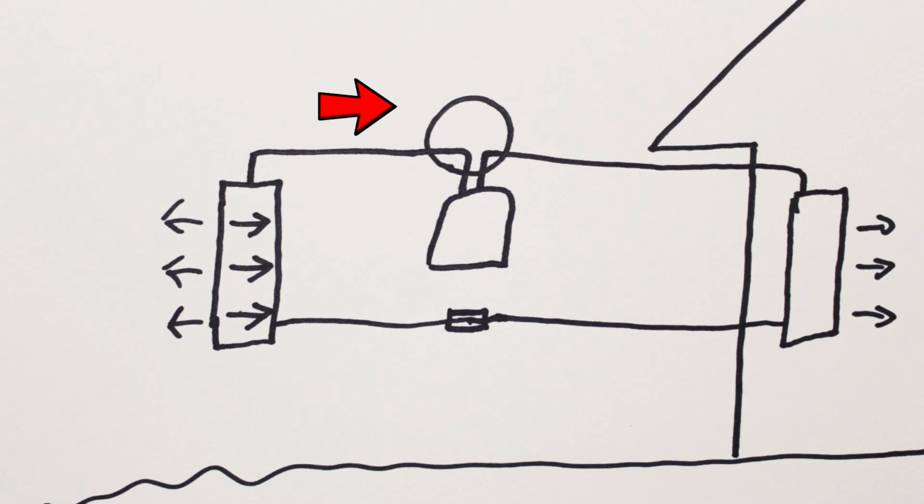And as the refrigerant is traveling through the system towards the compressor, and the compressor is basically the motor, the heart of this entire system, as that low pressure, low temperature vapor is coming out of the outside coil, going towards the compressor, the refrigerant absorbs heat from the air and it boils to a vapor. So it goes into the compressor as a vapor. When it comes out of the compressor, it's going to become a high pressure, high temperature vapor. And at this point, it's starting to go into the inside coil located inside the house.